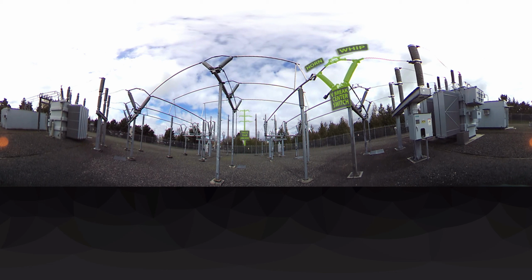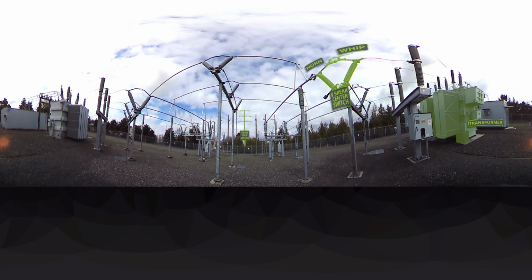Why is that? The reason is this breaker is located right next to our transformer. A transformer contains an enormous amount of copper wire coiled around an iron core. Because of the magnetic fields created by these coils, if this switch were to open to break the current, the sheer strength of the magnetic field coming from the transformer could keep current flowing by arcing through the air. So the whip and horn are here for added insurance to help break the circuit.